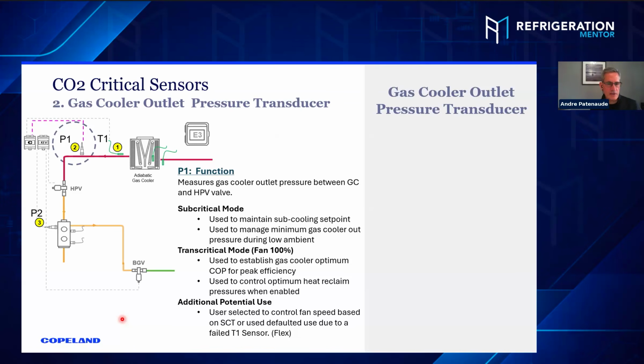So the next sensor is actually the gas cooler out pressure transducer, or sometimes we hear it called a drop leg pressure transducer. I'm showing it here at the gas cooler outlet line. But as we mentioned a while ago, that could be inside the building next to the high pressure valve. There's relatively no pressure drop between those two points, so it's not a big deal. But that sensor is super important. Yeah. So what does it do?